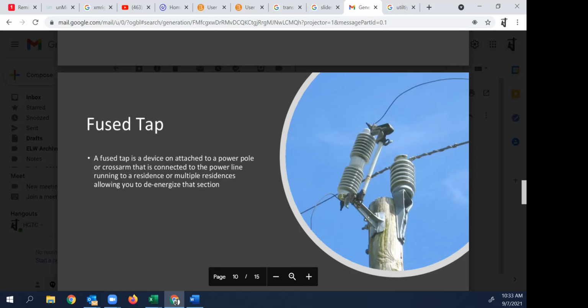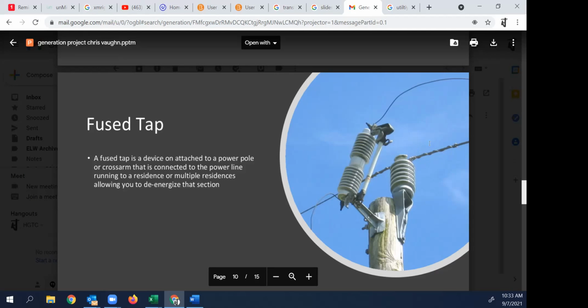Remember the substation breaker we had? It's like the breaker in your house, protecting our feeder lines in case of a short circuit. When we start tapping off our feeder lines to go down just a small street, do I want protection on that too? Yes or no? Yes, right. So I want protection down that short portion of street too, but I don't want to take out the entire feeder line.